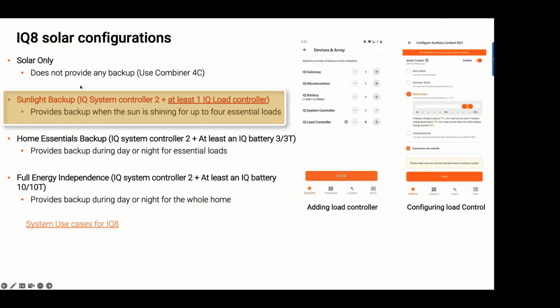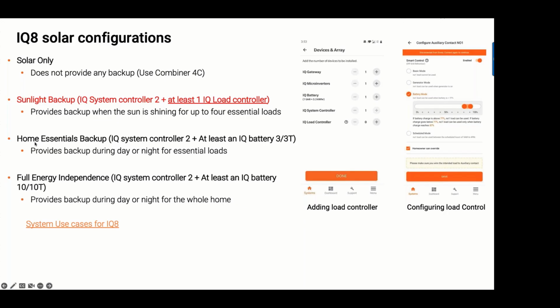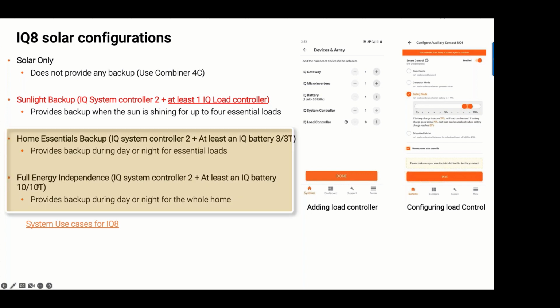To do this, there's a requirement. You're going to have to add a system controller, the system controller 2 specifically, and you're going to have to add an IQ load controller to manage loads. Beyond that, you can start adding batteries. Now, sunlight backup is solar only, so there's assuming no batteries to do backup. The next 2, home essentials and full energy independence, is adding batteries on top of your solar.